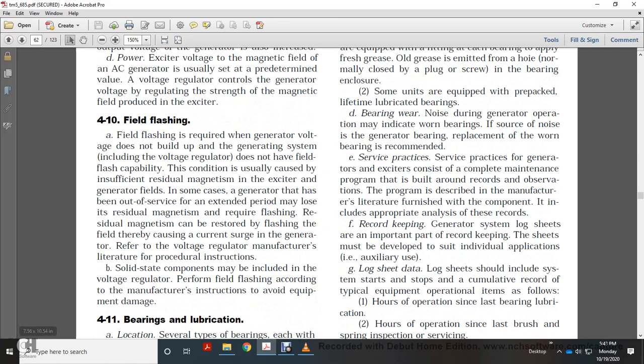Alright, 4-10, field flashing. A generator may be equipped with a voltage regulator but not build up voltage. Sets whose voltage regulator does not have field flash capability usually call for this condition due to insufficient residual magnetism of the exciter. In some cases the generator has been shut down for an extended period, which may lead to the residual magnetism requiring flashing.